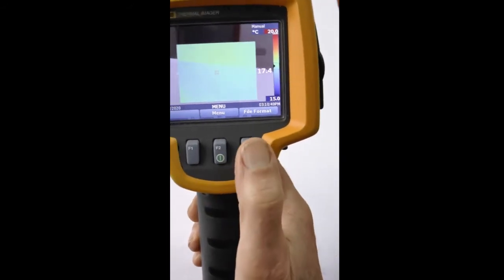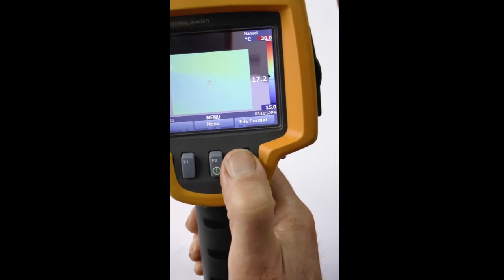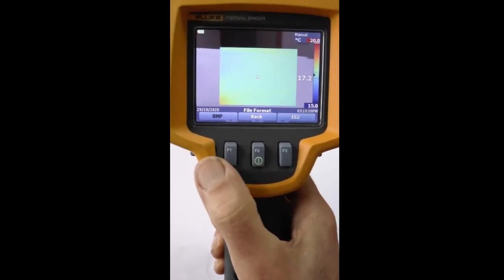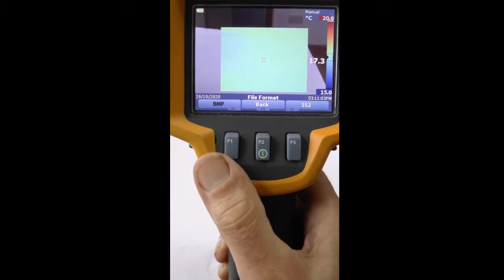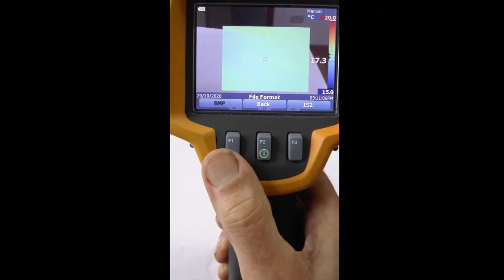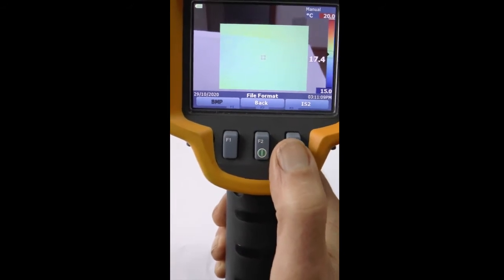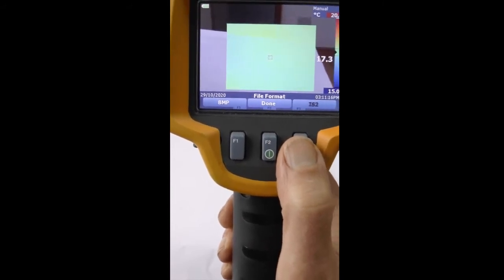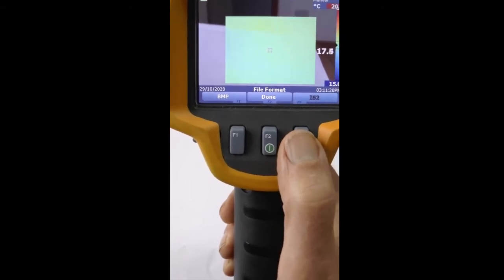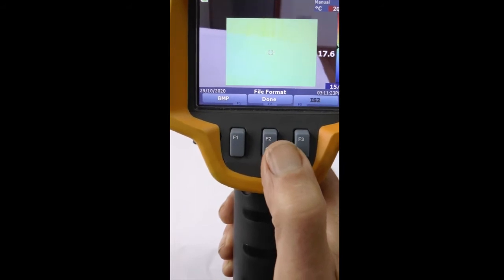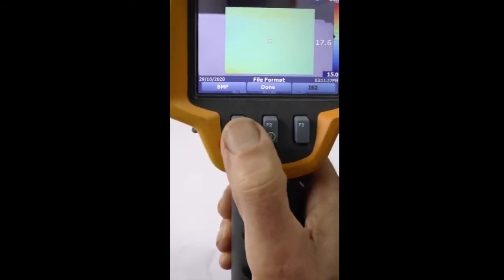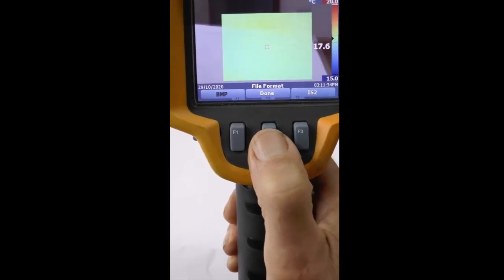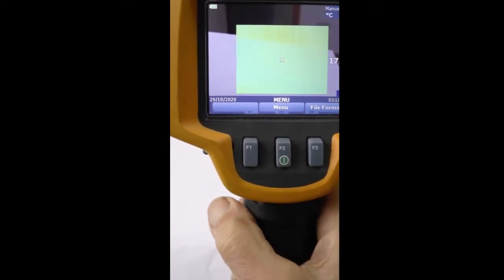finally on the right. That means this right-hand button will select the file format. We have a choice: on the left it's showing BMP, standing for bitmap, which is what I suggest we use. Over here I could select IS2. The problem with IS2 is it's a Fluke proprietary format that is only for use with the SmartView software, so if you're not going to use that, then you must choose BMP. When that's selected, you hit done, and now we know we've got the right file format.